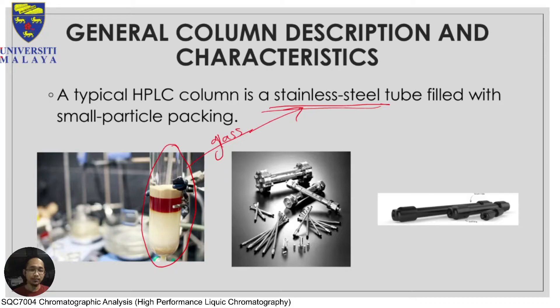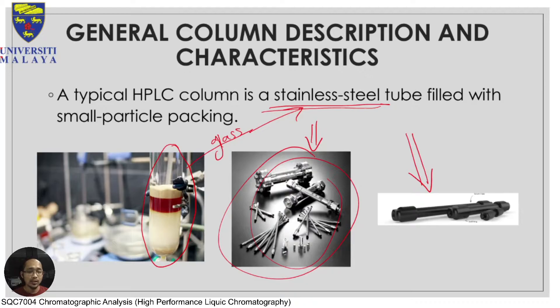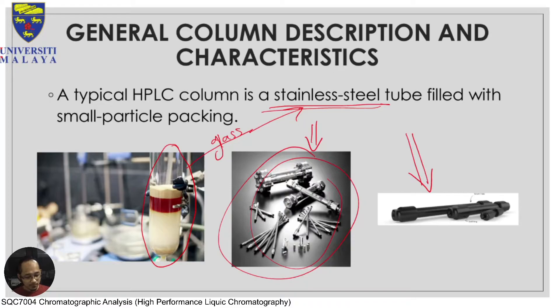Based on the influence of the Van Deemter equation and back pressure equations, some companies are now producing HPLC columns in more of a plastic — PTFE or PEEK material. The two most basic types of column are stainless steel and plastic tube. Column can be characterized based on four features: number one is the hardware itself — stainless steel or PEEK; number two is the modes.